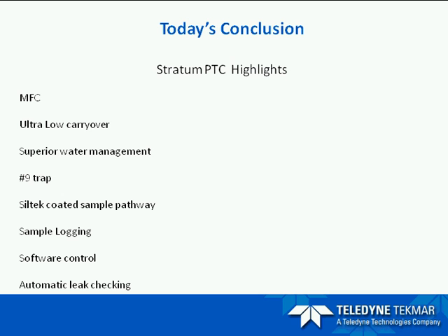As most of you are aware, helium is becoming quite scarce and expensive, so it's nice to have another gas alternative. Now, this patent-pending mass flow controller has the ability to vary flow rates in different modes. With the newly proposed changes, this tool will prove to be a very important part of your purge and trap analysis. The ability to vary your flow rates in different modes is going to greatly increase your sample throughput.